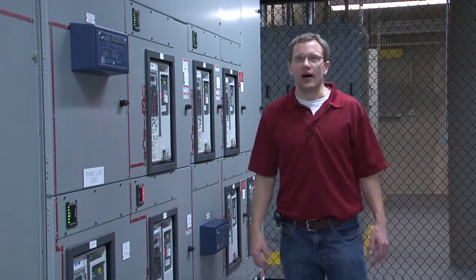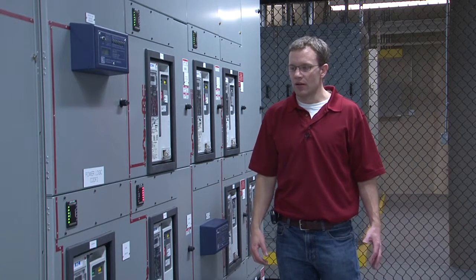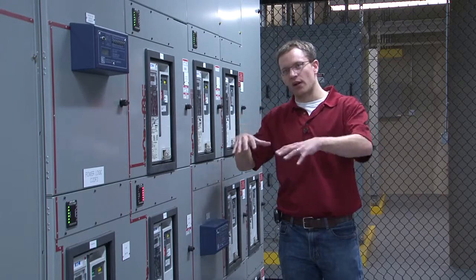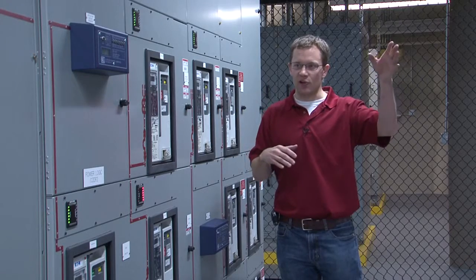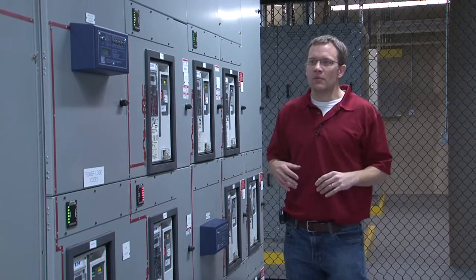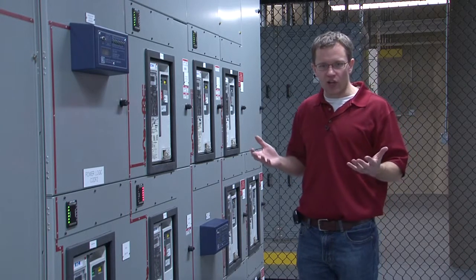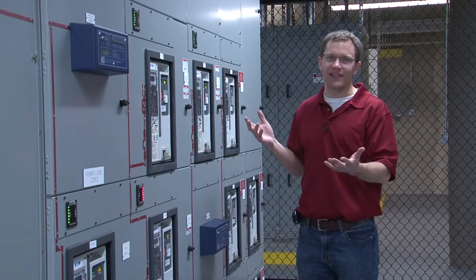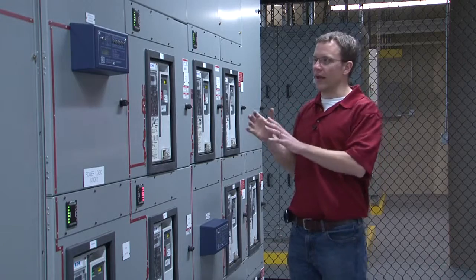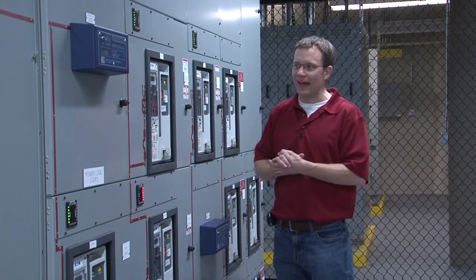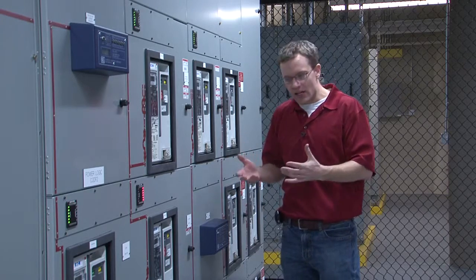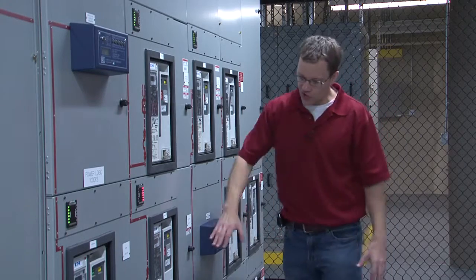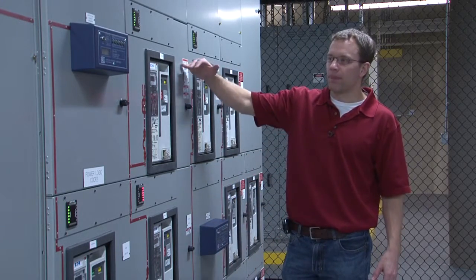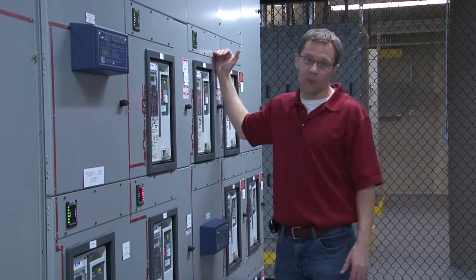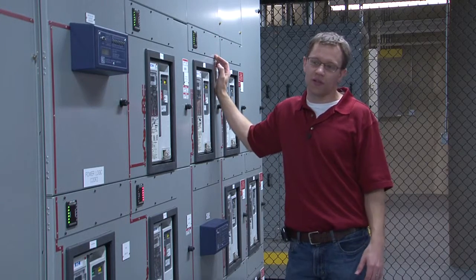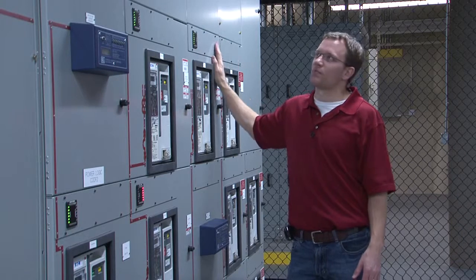Should also, just a general note, in this system, there is bus duct, and the bus duct runs between each of the UPS boards and MS3, and each of the mechanical boards and MS4. And so if one breaker is closed, anywhere connected to that bus duct, all of the bus duct is energized. So if you're at a substation, or if you're in a COD board and you want to shut it completely down, it's hard to do that. Even if you were to lock out all these breakers, while the distribution bus would not be hot, the line side of that bus duct, either for the maintenance bypass or for the load bank, could be hot if any of the other maintenance bypass breakers are closed. And that's just not a typical situation on most boards, but it is here.